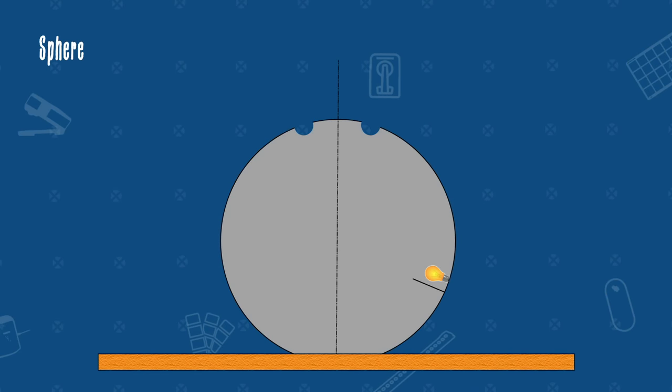Next are spherical instruments which capture light reflected from all angles of a sample. This measurement can include or exclude the surface appearance of your sample. These devices are commonly used for measuring color that has been applied to textured surfaces such as textiles, carpets, and plastics, as well as glossy or mirror-like surfaces, including foil printing.